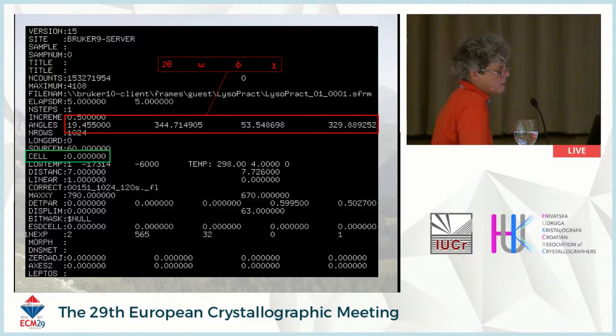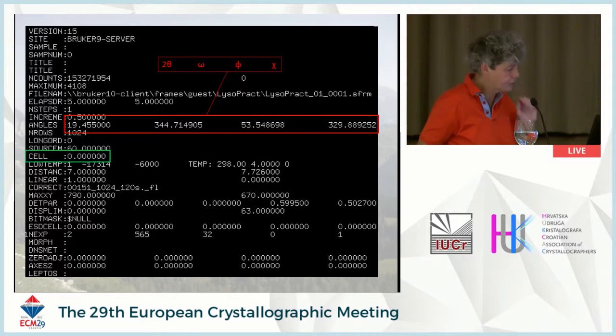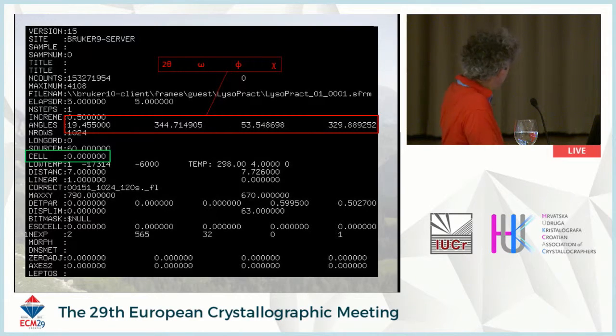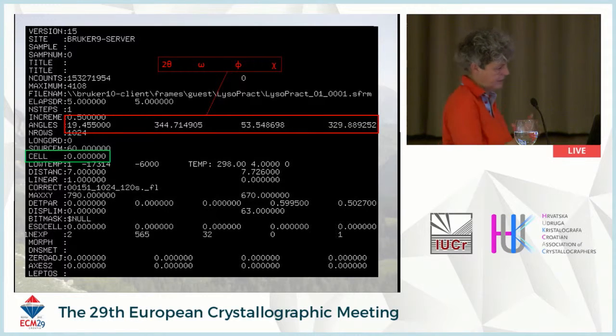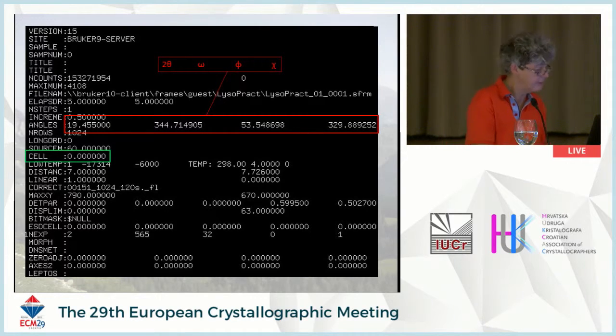The kappa goniometer header also has an entry for the unit cell, because in Bruker software such as APEX or PROTEUM you can determine the unit cell and insert it — which could be very useful metadata once the data have been processed. On top, the type of goniometer is indicated, so you know where all the goniometer axes are.